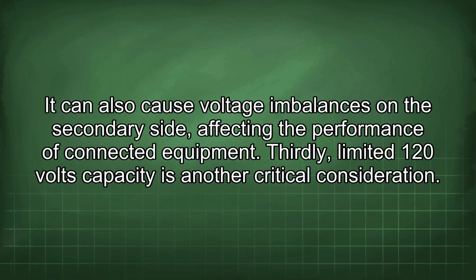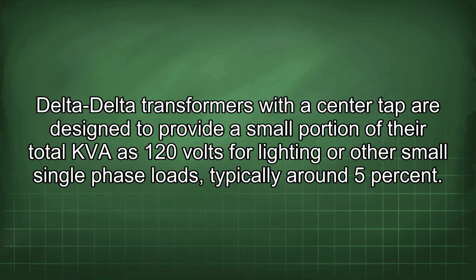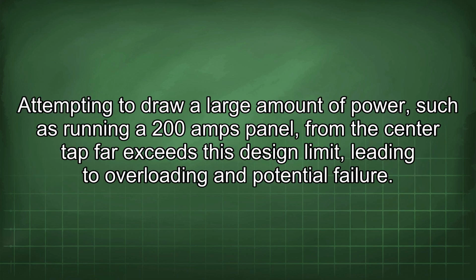Thirdly, limited 120 volts capacity is another critical consideration. Delta-delta transformers with a center tap are designed to provide a small portion of their total kVA as 120 volts for lighting or other small single-phase loads, typically around 5%. Attempting to draw a large amount of power, such as running a 200 amps panel from the center tap, far exceeds this design limit, leading to overloading and potential failure.